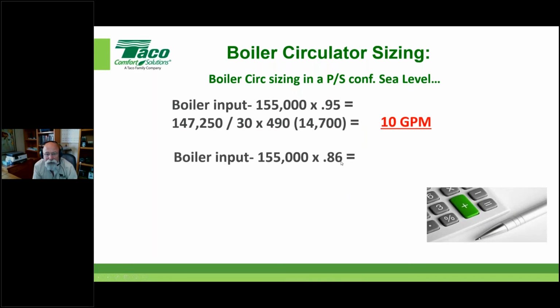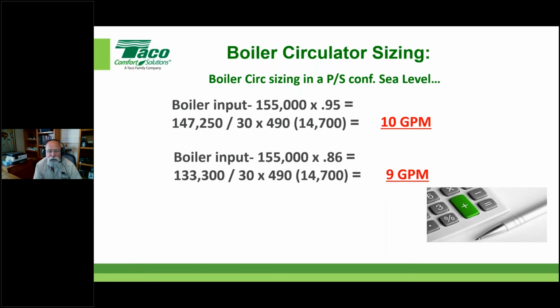Here's one, same calculation with less efficiency, and it gives you a slightly lower GPM required. If you're only going to be operating at 86% efficiency, then you don't need to size the pump for anything better than that, right? So again, 155, take this off of there, it gives you this. There's your delta T, there's your constant. You guys are used to 500, just keep using 500. Again, I'm splitting hairs, but for the most part, there's a reason that the number drops, and we talk about that on other webinars.